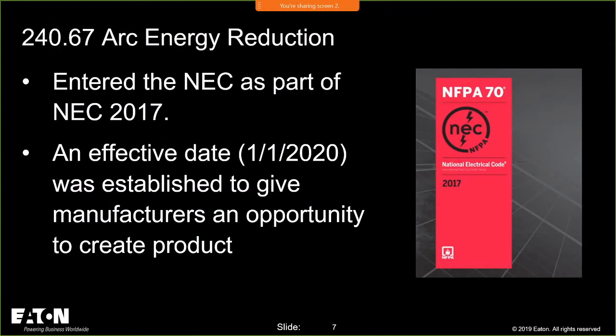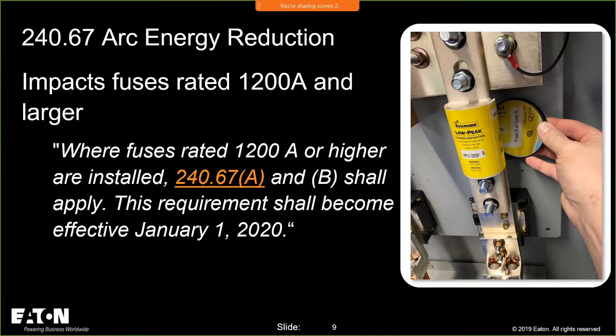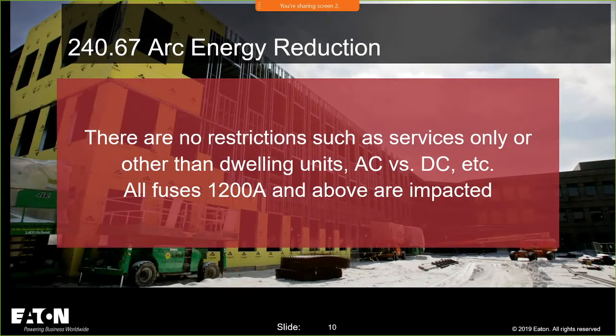Talk about it from an overview. We already know that it entered in the 2017 code. I already talked about that. It impacts fuses 1200 amps and larger. The way the language says it, I call them trigger points. Whenever you're looking at any code requirement, you've got to figure out, does it apply to me? So what this tells you is that if I have a fuse 1200 amps or higher installed, 240.67 A and B are going to apply, and the requirement shall become effective January 1st, 2020. Now, there's no restrictions, whether it's AC or DC or other than dwelling units. It's all fuses 1200 amps and above.